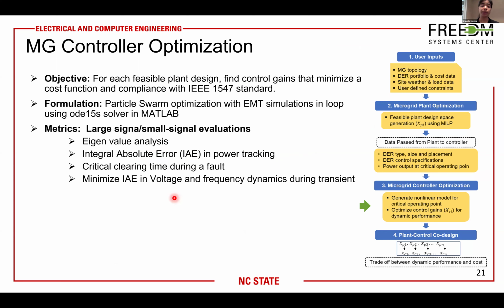Next is the control optimization block. Here the goal is to minimize a cost function, which is related to the dynamic performance metric, and adhere to grid standards like the IEEE 1547 standard. And we evaluate these optimal control gains using particle swarm optimization with EMT simulations in the loop.